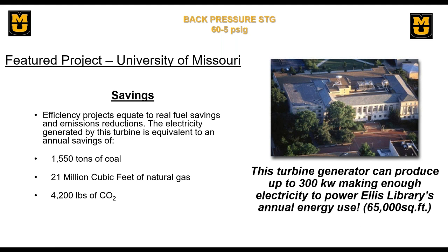I think to date, in the two and a half years that this unit's been operating, they've had a real cumulative savings of about $400,000. And just to give you a perspective, 300 kilowatts is enough power to power their entire library for a year, and that's about a 65,000 square foot building. Overall they said that in about 4 years this unit's going to pay itself off. So those numbers seem to be in line with the scenarios we were just looking at. Thanks to Harry Frank and the people at Mizzou for providing some of this information and being a part of a successful project like this. Yeah, absolutely.